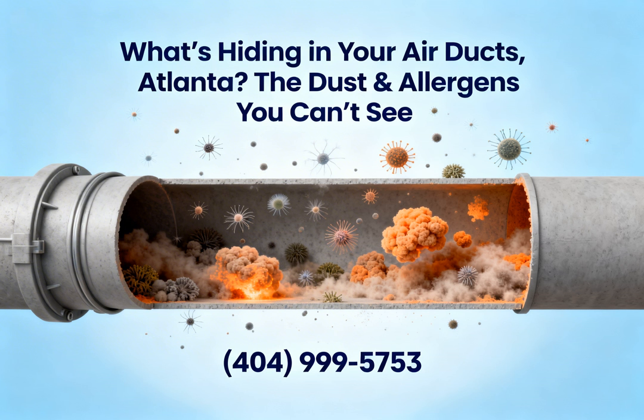And because it's under negative pressure, the exact millisecond that sludge is broken loose from the wall, the vacuum instantly rips it out of the airstream and pulls it to the HEPA filter. There is no opportunity for the debris to settle or escape. It's a highly synchronized process: agitation immediately followed by extraction. And that leaves us with an incredibly clean, bare duct.